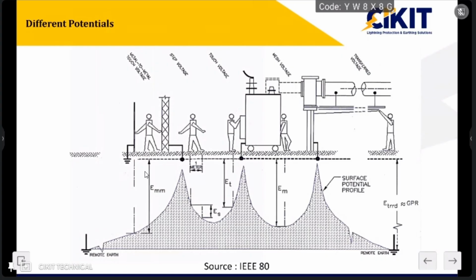Whenever we are discussing substations, four more important potentials come into the picture. We will be concentrating mainly on two potentials, that is step and touch voltages. But apart from these two voltages, there are two more voltages that also have to be considered. If one person is standing inside this substation area and making contact with a grounded object, here you can see the person is standing here and making contact with the structure which is at a very high potential. The person's foot is at low potential whereas the structure is at very high potential. Because of this difference in potential, current may flow through the body and he may get electrocuted. This is called touch potential.